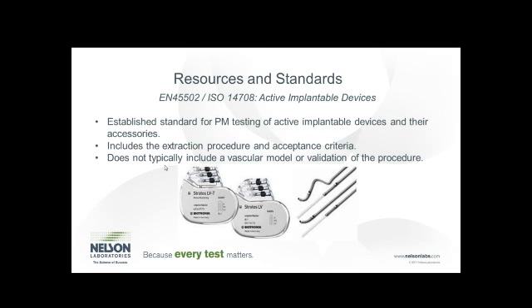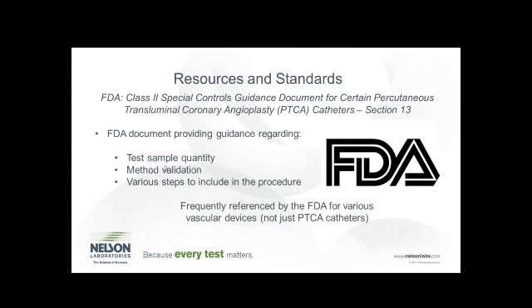EN45502 and ISO 14708 is an established standard for particulate matter testing of active implantable devices and their accessories. It is a compendial method that includes the extraction procedure and the acceptance criteria, so it's not necessary to come up with your own procedure or acceptance criteria. It does not typically include a vascular model or validation of the procedure, making things quite a bit simpler. It's a semi-involved test whereby the device is placed in saline and orbital shaken for 8 to 18 hours at physiological temperature — 37 degrees C plus or minus 2.